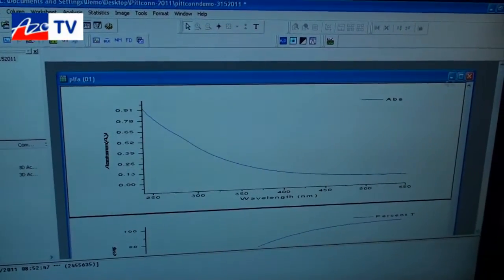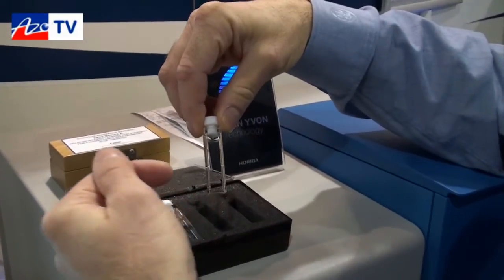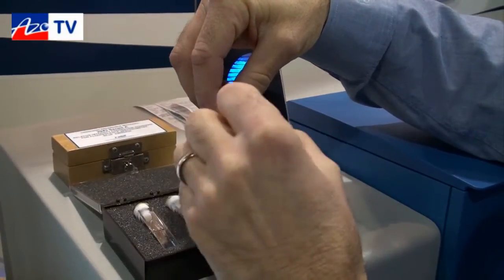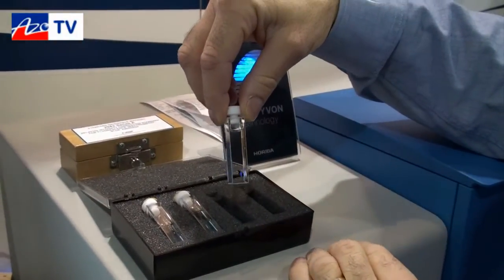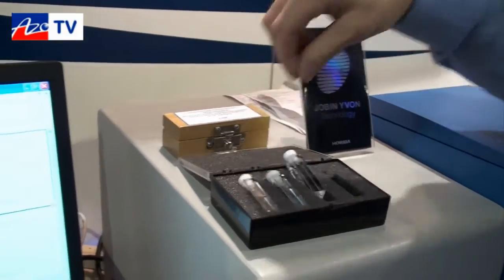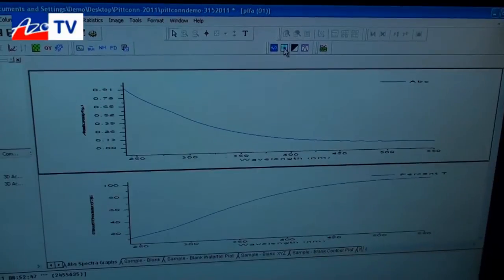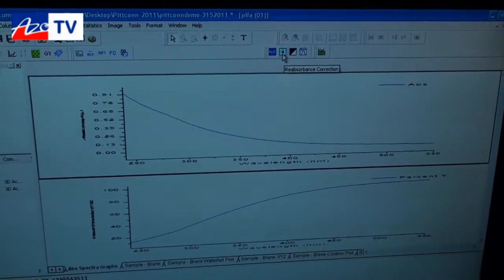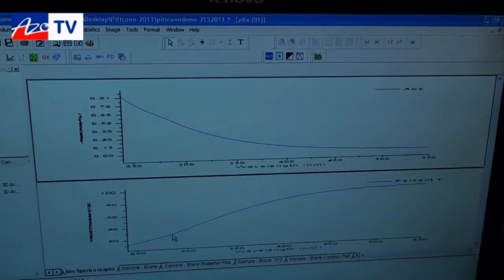The other reason the absorption is important is because the fluorescence sample holder cuvette, the sample that's inside, when the exciting light passes through and the fluorescence is emitted, part of the fluorescence light can be reabsorbed and that can distort the spectrum. So we have a special algorithm for this instrument called the reabsorption correction. What that does is it corrects the fluorescence with the excitation spectrum to yield an undistorted fluorescence spectrum.